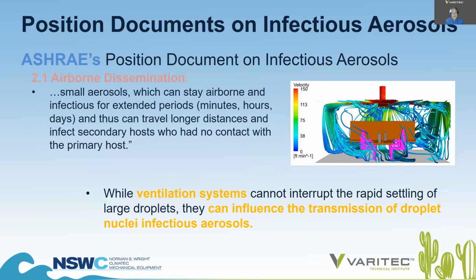Regarding airborne dissemination, ASHRAE goes on to say small aerosols can stay airborne and infectious for extended periods, minutes, hours, days, and that's a big one, days, and thus can travel longer distances and infect secondary hosts who had no contact with the primary host. While ventilation systems cannot interrupt the rapid settling of large droplets, and we'll cover that in greater detail in the future, they can influence the transmission of droplet nuclei infectious aerosols. So that's an important distinction. How your HVAC system conditions the air and delivers the air within the built environment can influence transmission by droplet nuclei viruses that could be concentrated within the space.